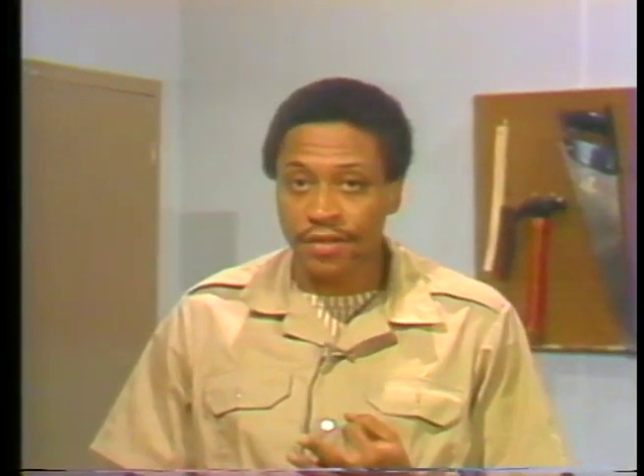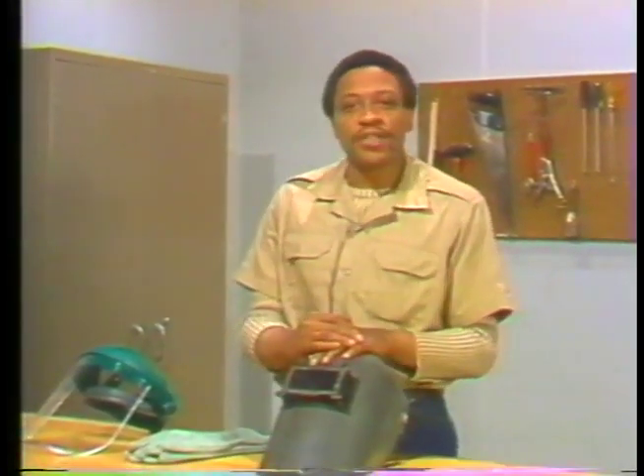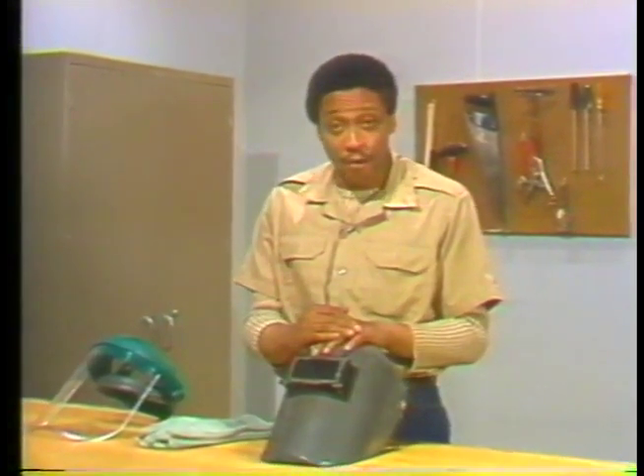We're now finished with our discussion of tube repairs. You should now know what causes tube failures, what these failures look like, and the four ways failures can be fixed: replacing a tube section, cladding a thinned area, closing a rupture, and making a window repair. Remember, only certified welders can perform the actual welding inside a boiler. Always keep safety in mind, follow all safety precautions, check your safety manual, and review the material before actually starting work on tube repairs.